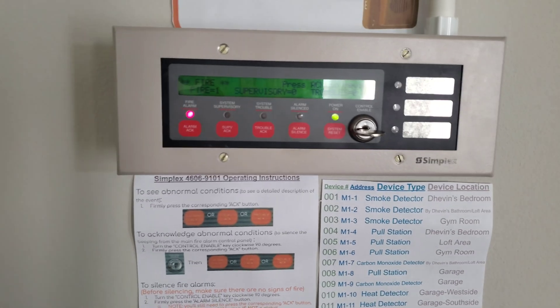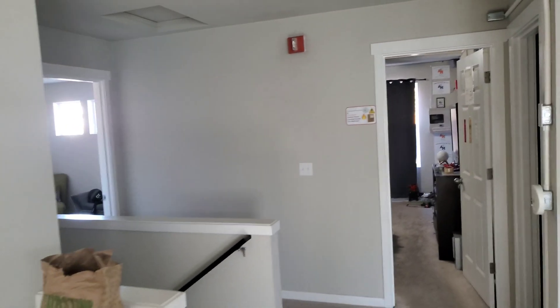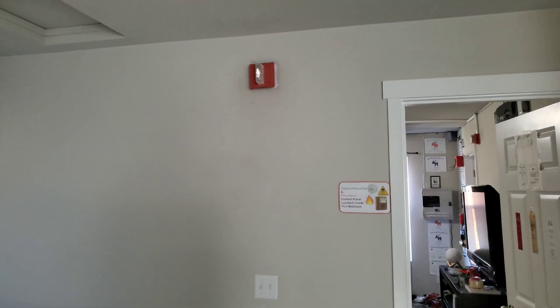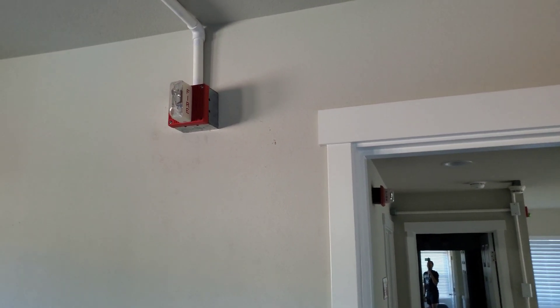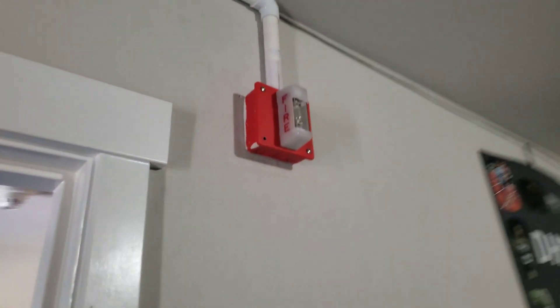This is one that's actually really quiet — insane how quiet it is. The coding option was 4002 style code 3, with audible silence still remaining. Upstairs is pretty much the unsynchronized section, where it doesn't really matter a whole lot because you're not viewing two strobes at once. That strobe is crazy though.